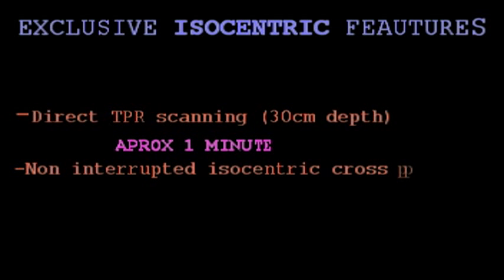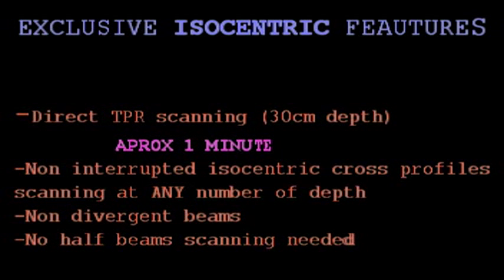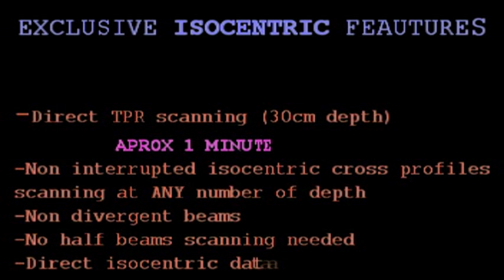Exclusive Isocentric Features: Direct TPR scanning 30 cm depth, approximately 1 minute, non-interrupted isocentric cross profile scanning at any number of depths, non-divergent beams, no half-beam scanning needed, direct isocentric data input into treatment planning.